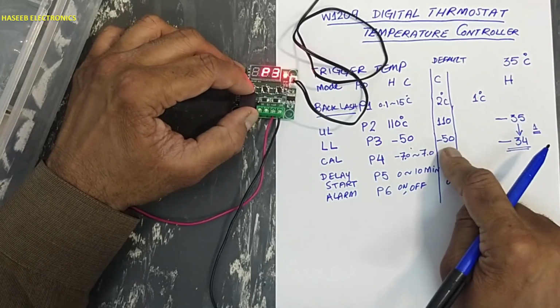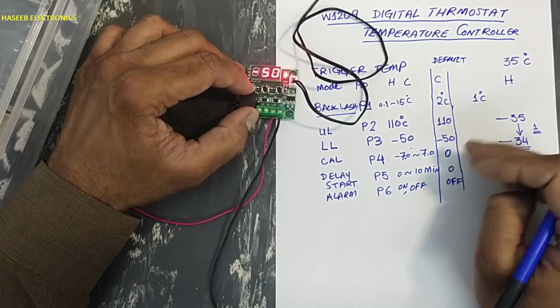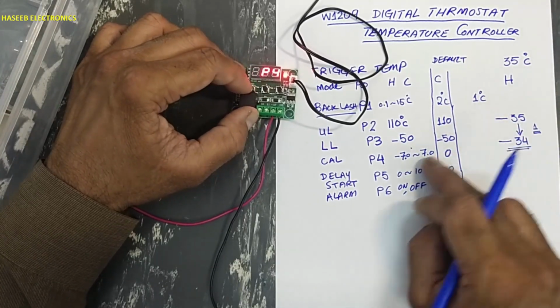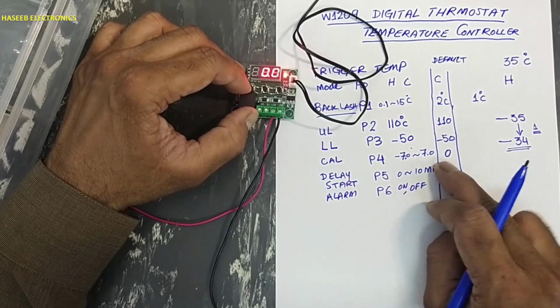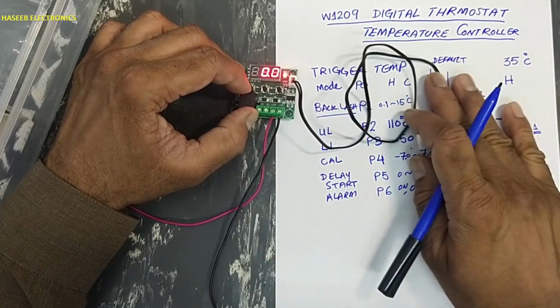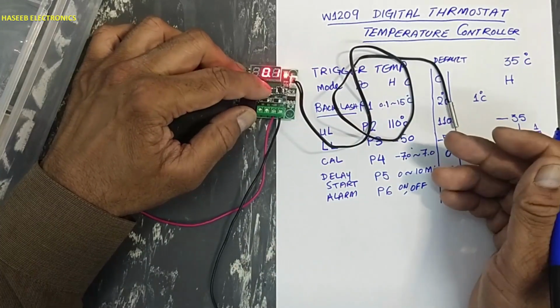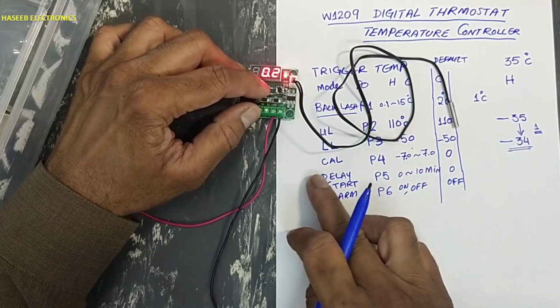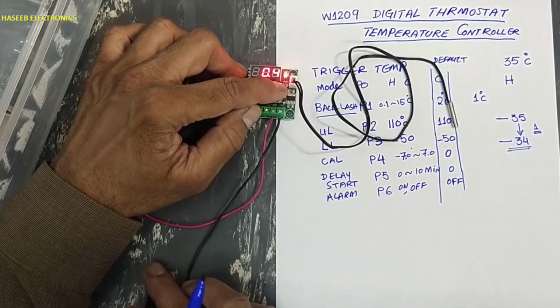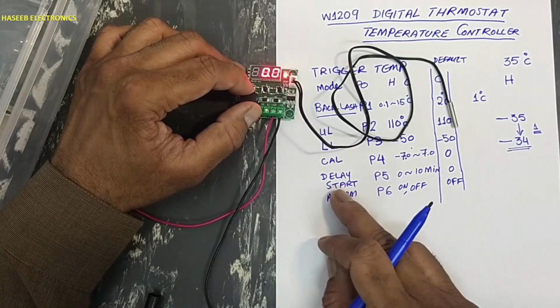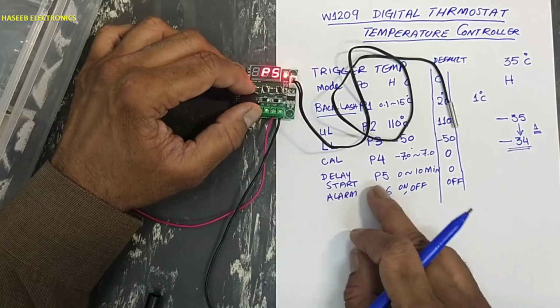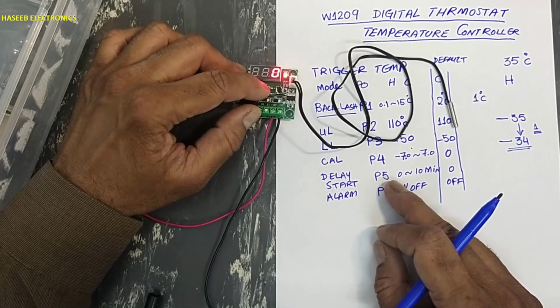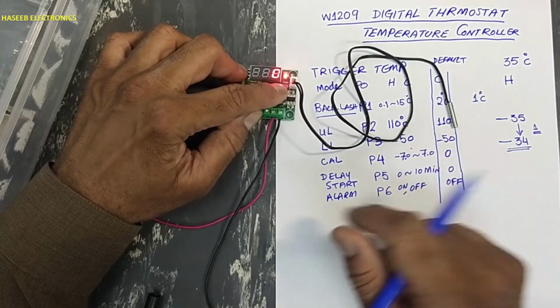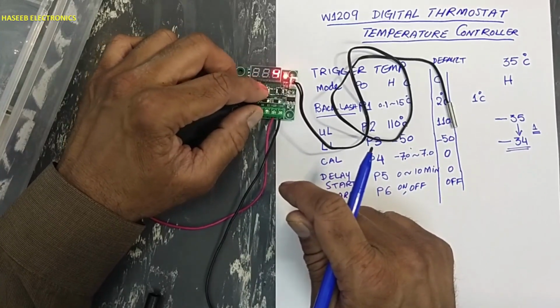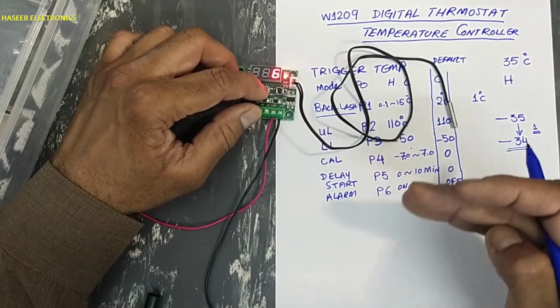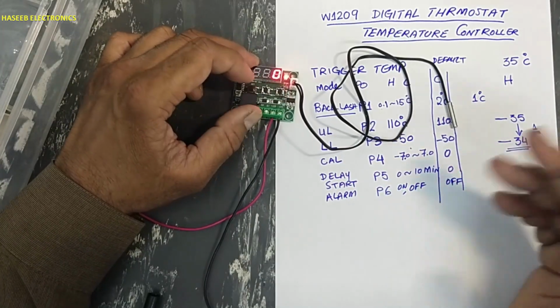P3, minus 50, no need to set any borderline. P4 calibration. Let's assume that this probe is reading accurate. If we are facing any problem, there is difference, we can add correction from here, plus or minus. Normally it is 0. Then P5 delay start. Set 0 from 0 to positive 10. How many minutes we want to produce a delay? We don't want to set a delay.